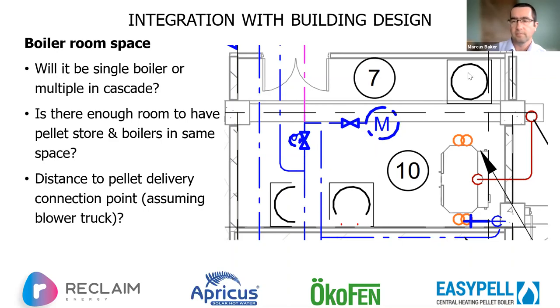And then in here, you can see, I think this is a 1,000 litre buffer, as much just for hydraulic separation as anything else, because we've got multiple loads at multiple temperatures coming off. And then this will be a couple of, I think, 1,500 litre or possibly 1,200 litre domestic hot water cylinders with decent sized coils in them. So you've got separation with the potable and the non-potable, and then also coming off here will be heating to a pool and a spa. And I think we're even providing some heat into the HVAC system. But it just gives you an idea, it's not a huge space, and we're able to get plenty of energy in there.